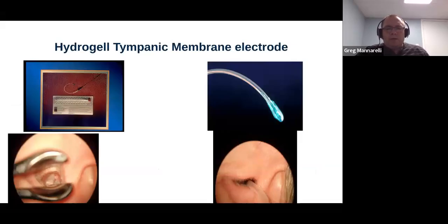How do you record this? Well, you record this by getting an electrode as close to the cochlea as possible. You can do it with metal wrapped insert headphones, which they sometimes call tiptrodes, but we find those responses typically not reliable enough to interpret on a regular basis. So you're generally going to want to use some sort of tympanic membrane electrode.